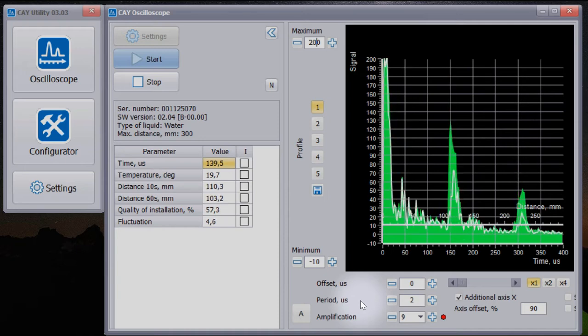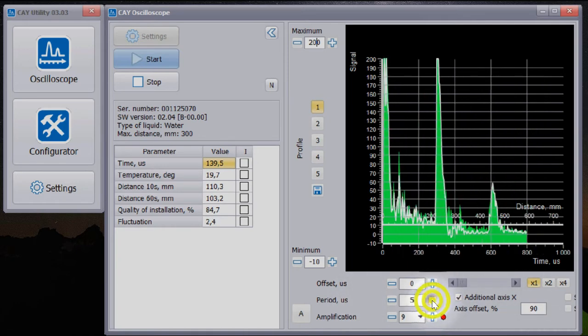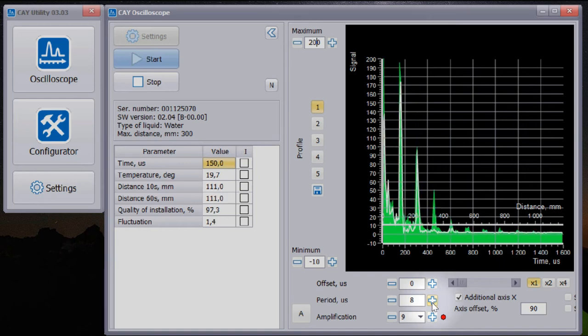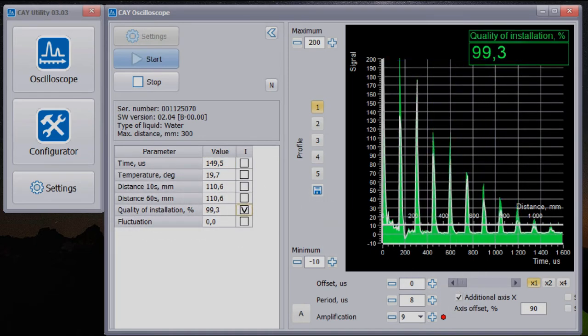Move the sensor and try to receive as many reflections as possible. Important: reflections must be declining to the right side of the scale. The second criterion is installation parameter quality. We have 100% now. After the best installation place was found, we cover the sensor surface with glue and fix the sensor with metal ties.